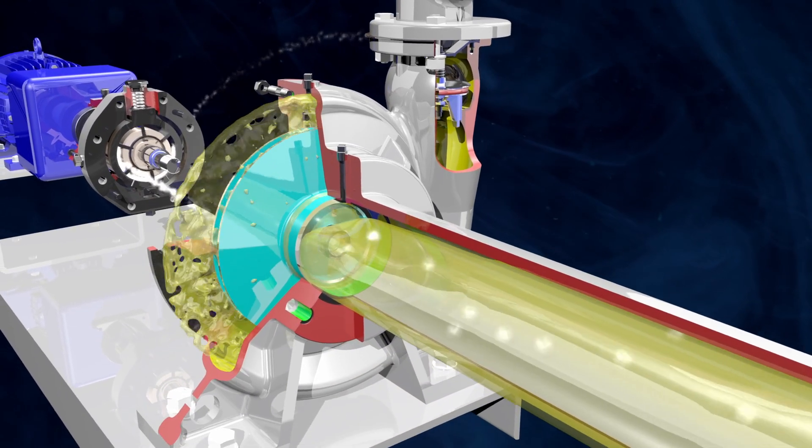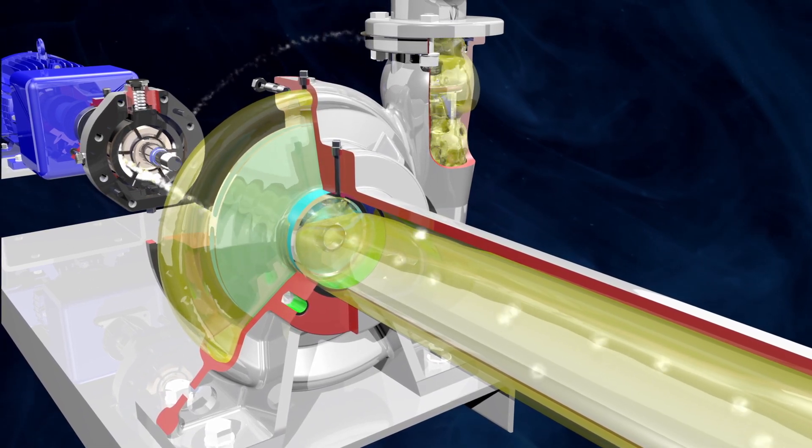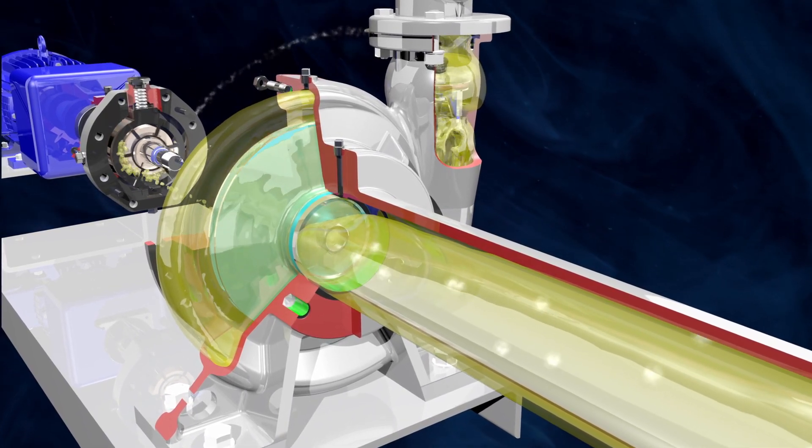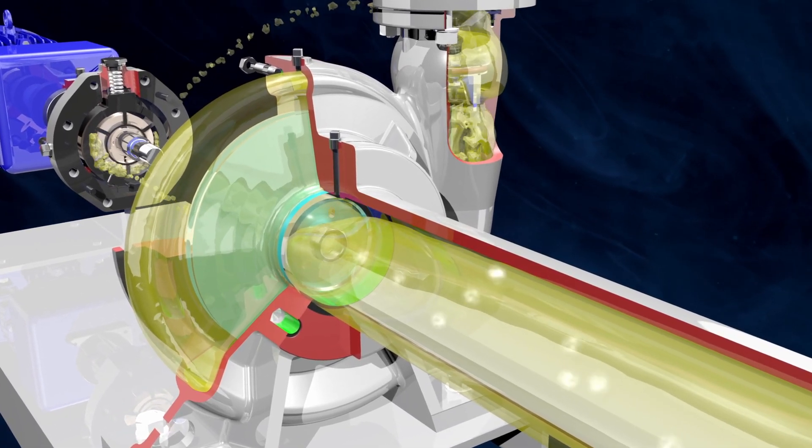As the centrifugal portion comes online and all air and vapor are expelled, the impeller creates liquid flow, shifting the priming pump into neutral, where it continues to operate with minimal liquid flow.